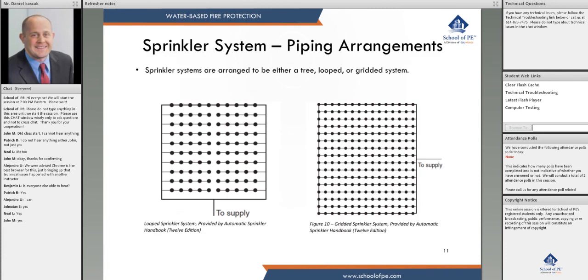We also have looped and gridded systems. In a loop system, the branch lines still have one path to feed, but the cross main is looped so there are multiple paths back to the water source. After getting through a branch line you can go either direction, which cuts down on friction loss. In a gridded system, the cross mains are looped and the branch lines are also interconnected, so at any sprinkler you can go in either direction.